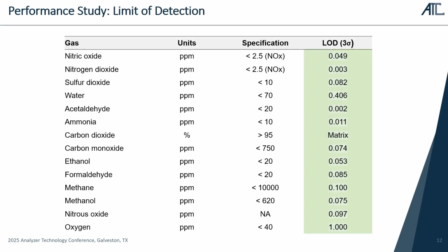So here's a summary of the results of the limits of detection compared to the specification. You can see our 3 sigma results in the sample matrix are well below the specified limits, even with the high concentrations of potential interference and high levels of CO2. So we're roughly 20 to 50 ppb, or 20 to 50 times lower than the specification, which allows us to have a lot of faith, especially if the specifications were to be lower over time. It allows us to feel confident that we're going to be ready for that.